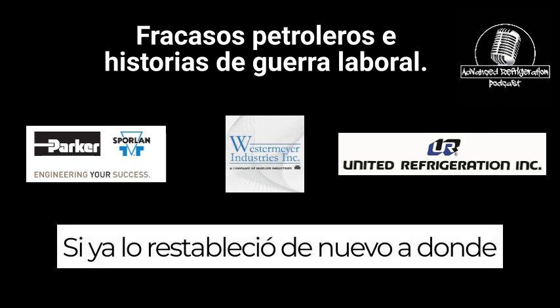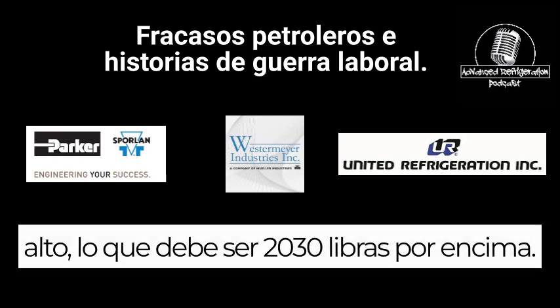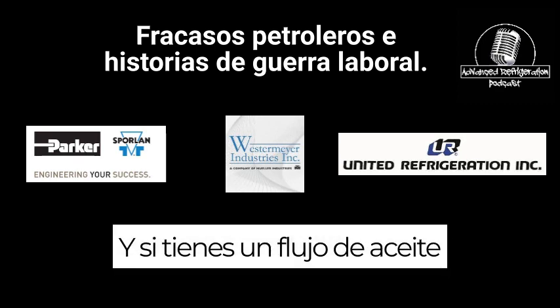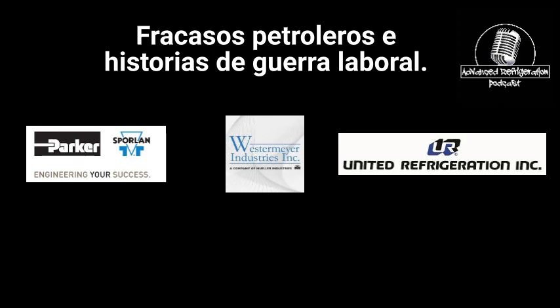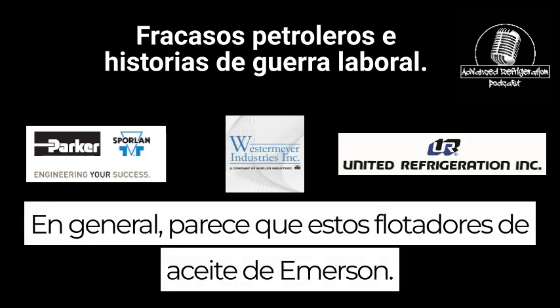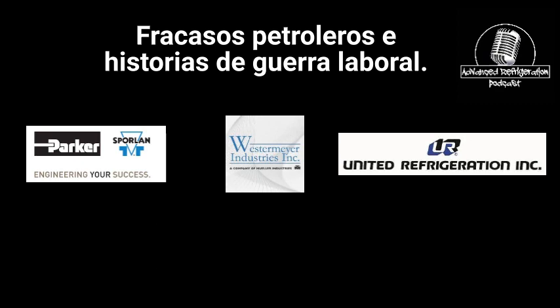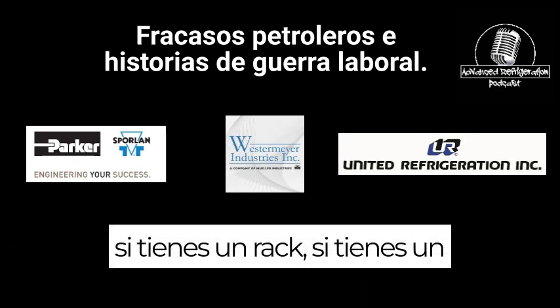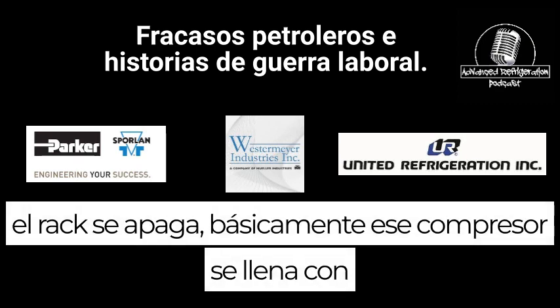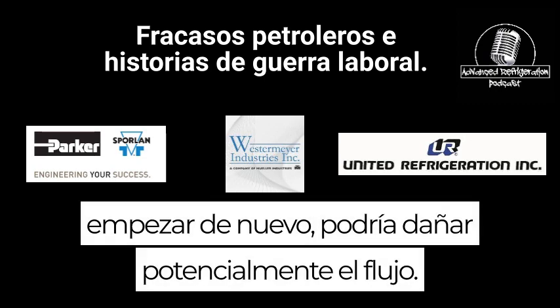If you already reset it back to where it should be, and the oil pressure is not too high, whatever it should be, 20, 30 pounds above, and you have an oil flow failure, then you need to change the float now. Generally, it seems like these Emerson oil floats, I don't know if you see a lot of them, Brett, seem to fail a lot. Well, that could be due to a rack shutdown, where basically that compressor fills up with liquid and then that rapidly expands when it goes to start back. It could potentially damage the float.